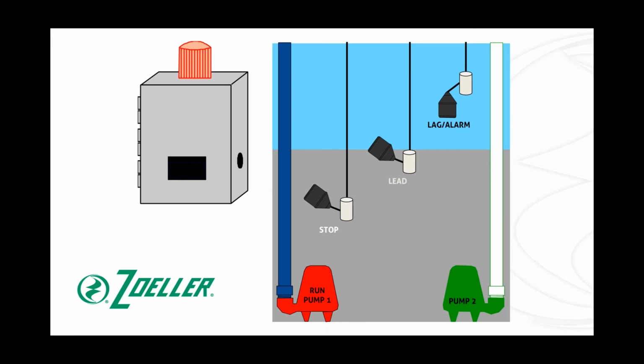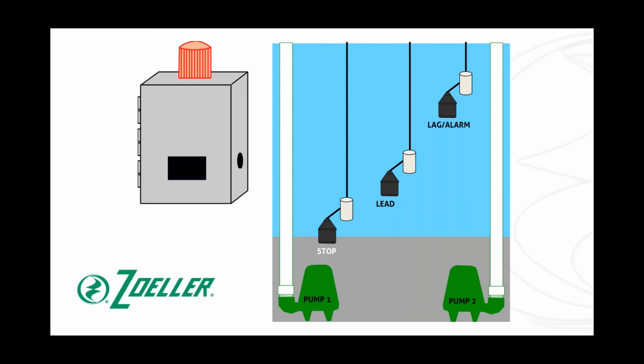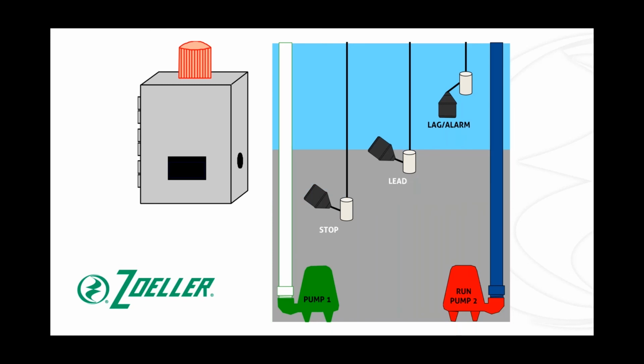And when that happens, pump 1 comes on and water is being discharged. So pump 1 runs until the water is discharged to such a point that the stop float drops out. And when it does, the control panel shuts off the pumps and it's ready for the next pumping cycle. So let's go through it again. Now this time the water level comes in, the stop float comes up. As water level continues to rise, we now activate our start or our lead float.